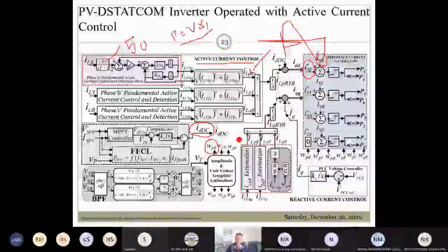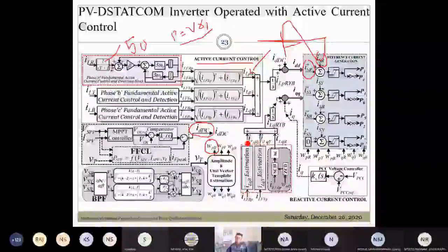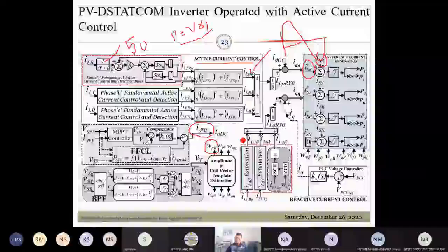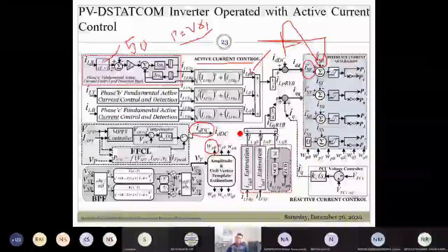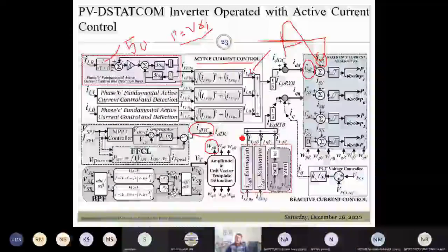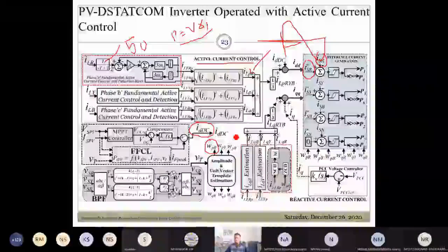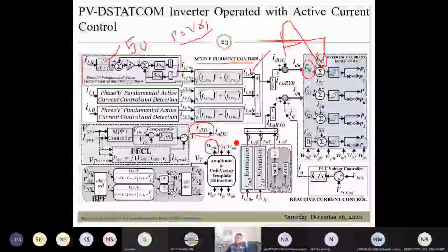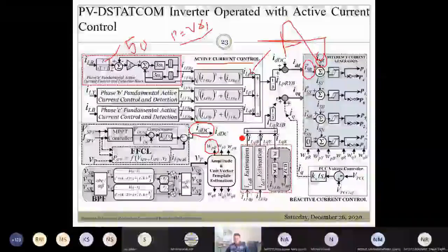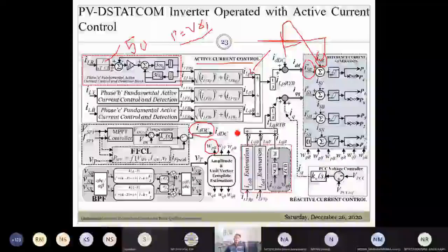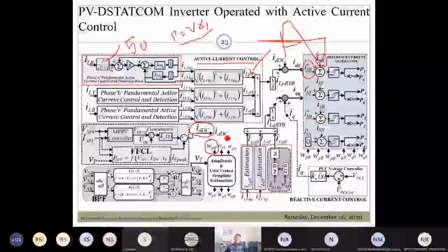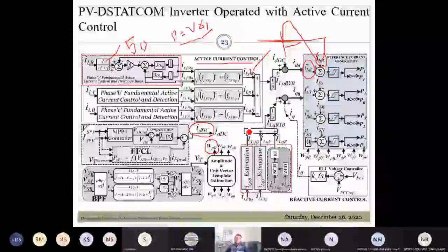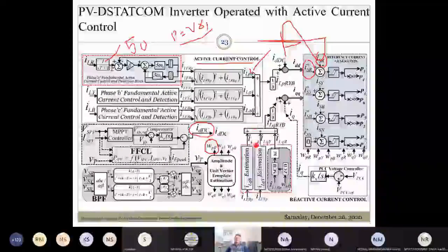I want you to understand that at present, if you refer to the IEEE standard 1547, the 2003 standard, IEEE 1547.2, then reactive power support through these PV inverters is forbidden. However, the potential of this reactive power support capability of the inverter is anticipated to be recognized as the penetration of renewable energies increases.